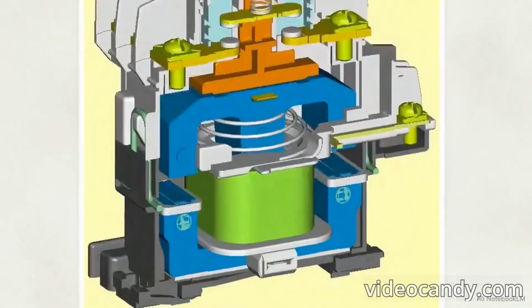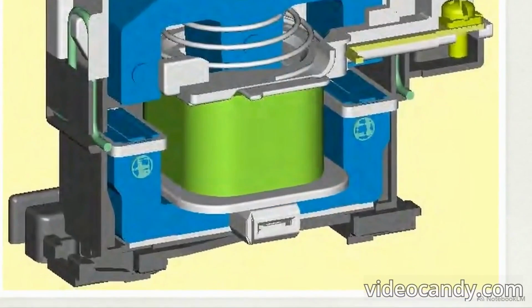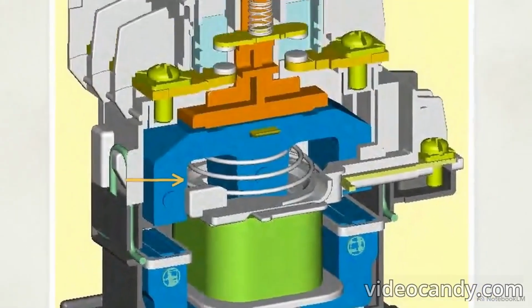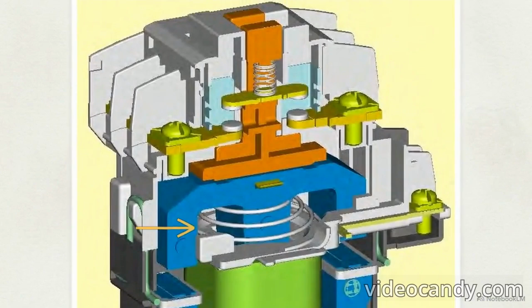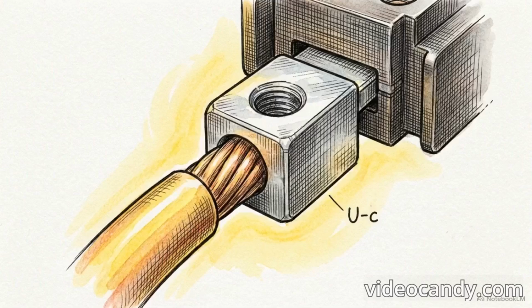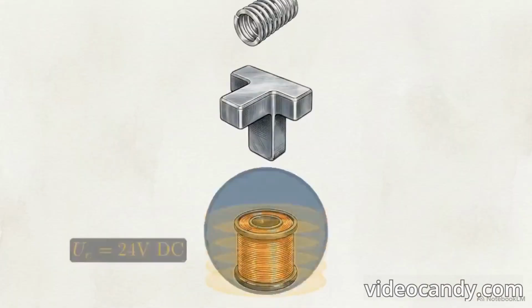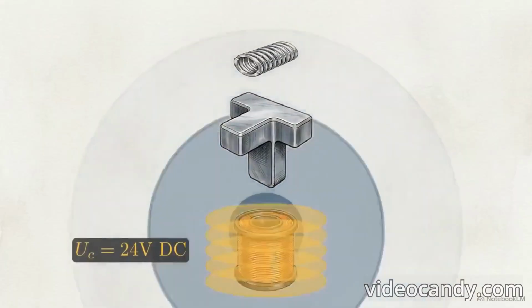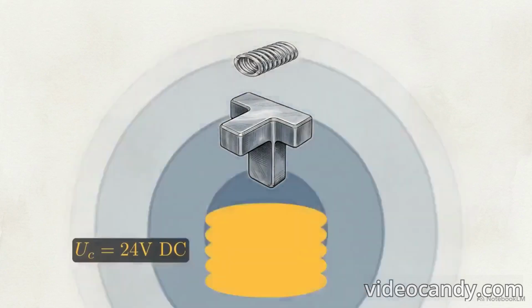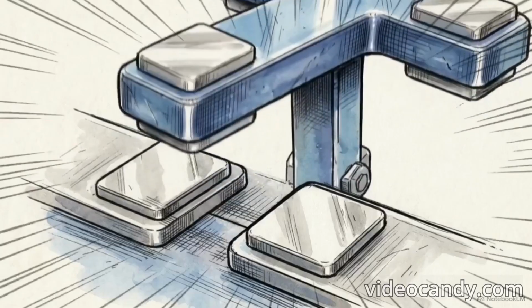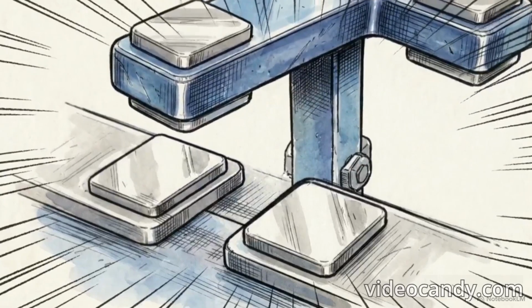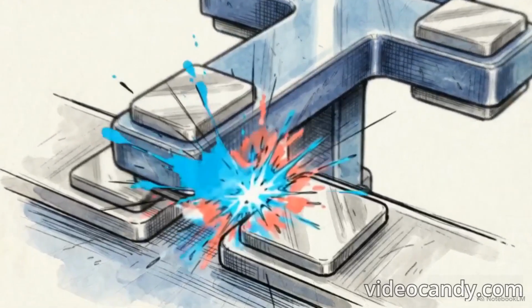This 3D cross-section reveals the physical balance driving the contactor. At the base is the fixed core wrapped in a copper coil. Above that is the moving armature with its contact pads, held apart by a central mechanical backspring. The operational sequence begins when control voltage, referred to as UC, is applied to the coil. This energizes the copper windings, generating a localized magnetic field strong enough to overcome the physical resistance of the backspring. The magnetic force pulls the armature downward.